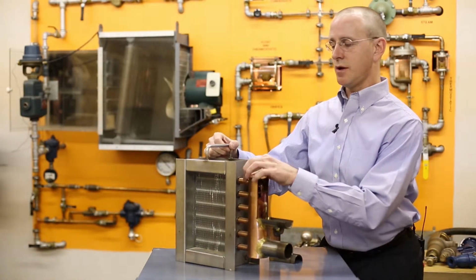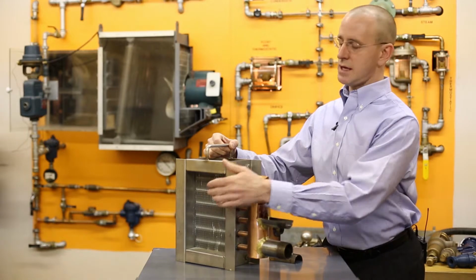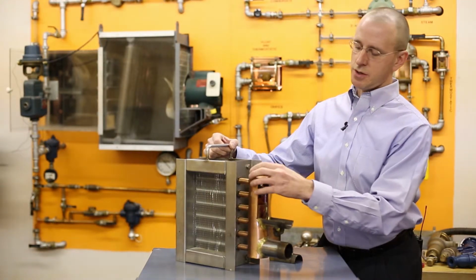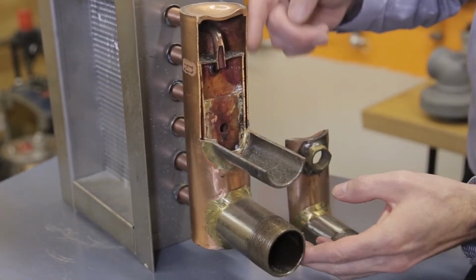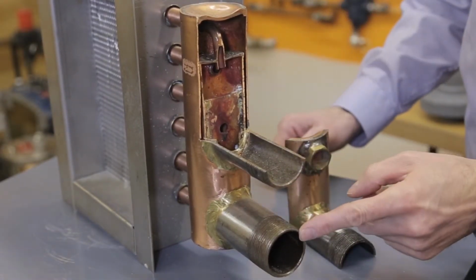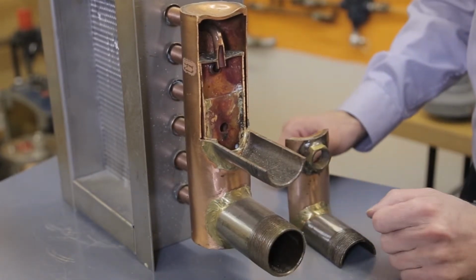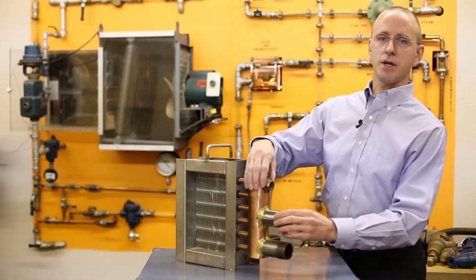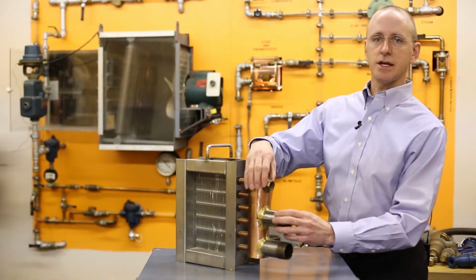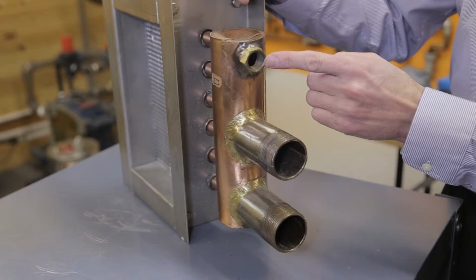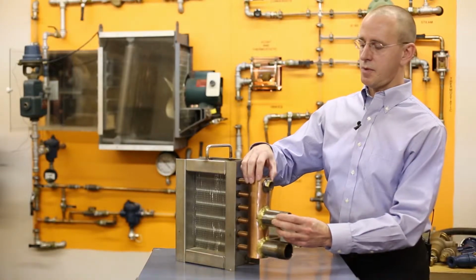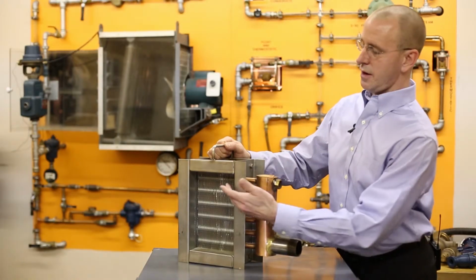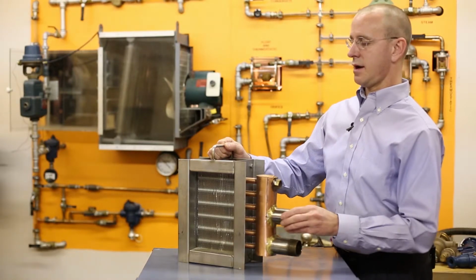It's the outer tube that's in contact with the finned area, and that's where the condensing occurs. Then that condensate travels down the outer tube to the outer header, which is then connected to the condensate connection. Then the condensate drains out and goes to the steam trap, which is piped downstream. Because this outer header is our steam condensate header, that's where the condensate velocity or steam velocity is near zero. That's a good place to pipe in a thermostatic air vent and vacuum breaker. The air, of course, does blow across here where it's heated.